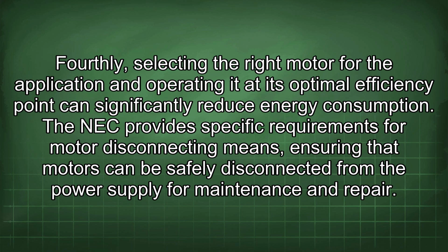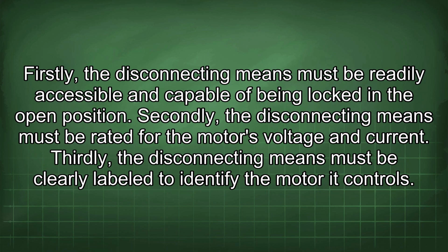consumption. The NEC provides specific requirements for motor disconnecting means, ensuring that motors can be safely disconnected from the power supply for maintenance and repair. Firstly, the disconnecting means must be readily accessible and capable of being locked in the open position.